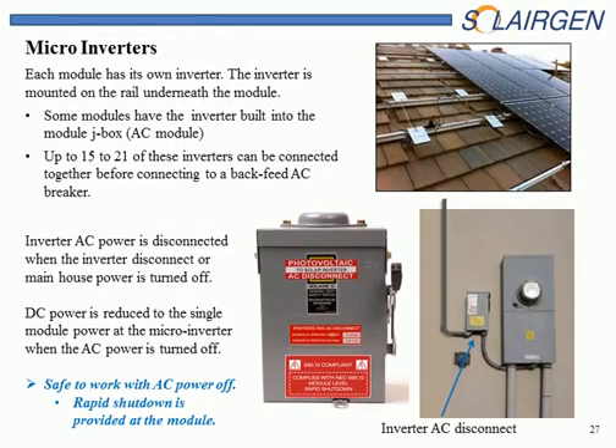So with a microinverter, basically they have an AC circuit that loops from one microinverter to the next, and they may have 15 to 21 of these inverters with their accompanying modules in a single circuit that back feeds into a main panel. There's disconnects up there underneath the modules for the DC and for the AC, but those are not readily accessible disconnects. You don't want to try to get into that.